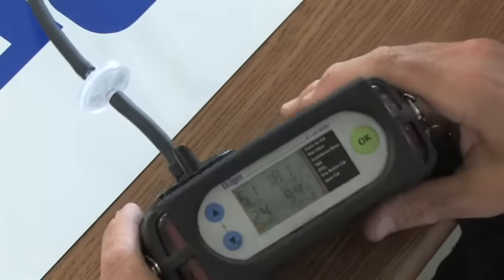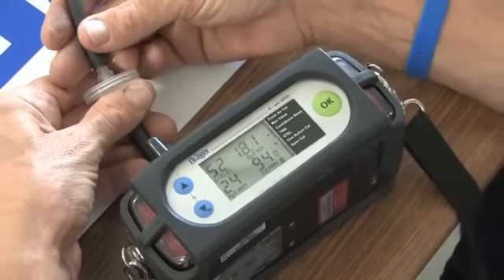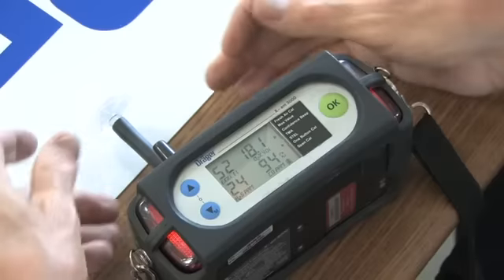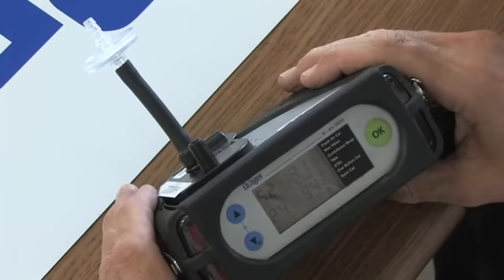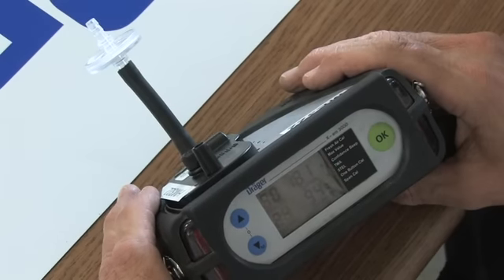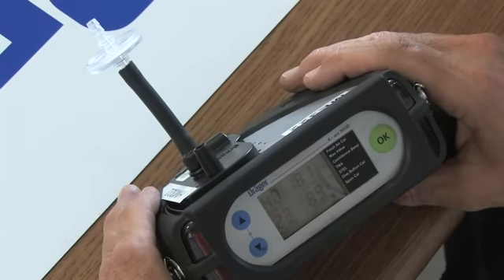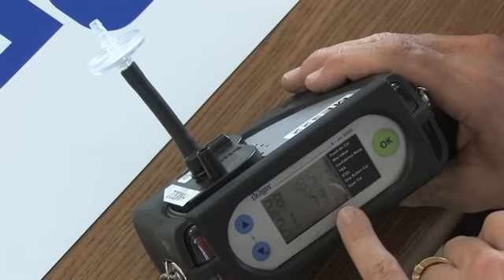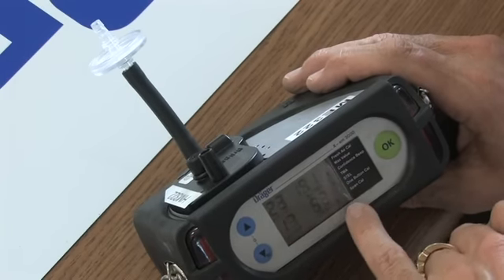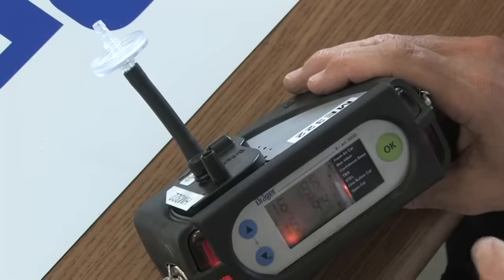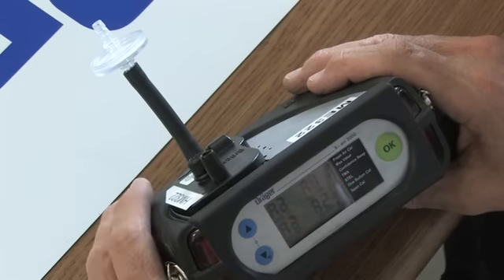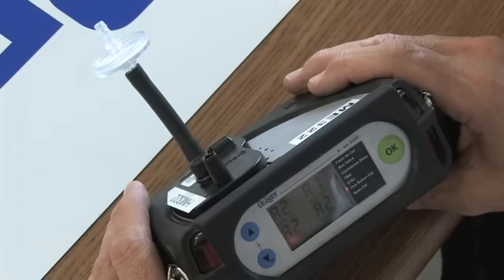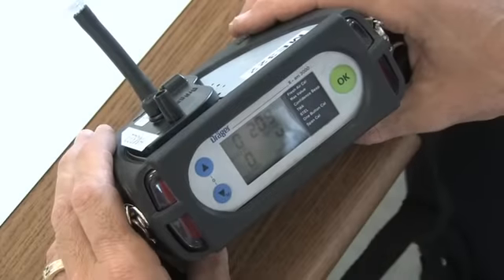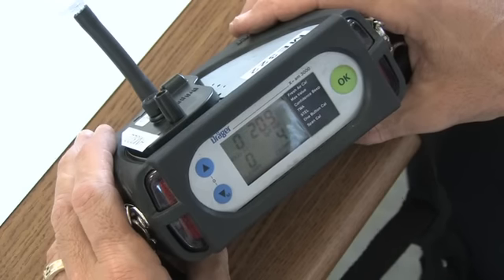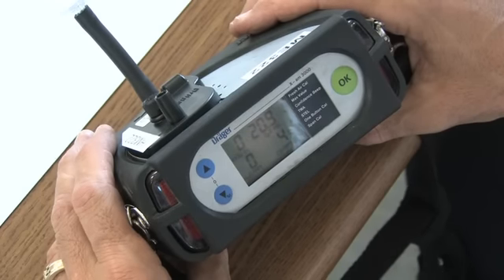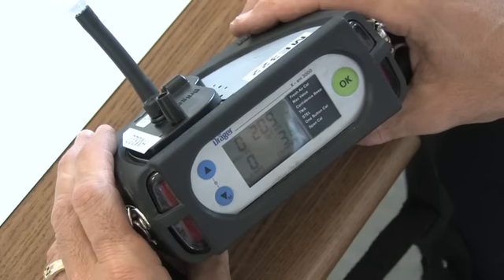So I'm going to remove the gas. And I'm going to let this clear. Notice also above the battery icon are two little arrows, one kind of looping upwards, the top one looping downwards. That tells me that my pump is operational and flowing. So, the bump test on this meter was successful. I'm just waiting for the CO to clear.